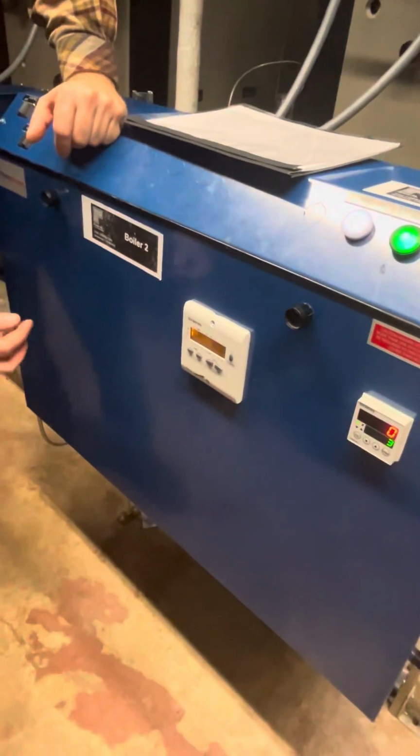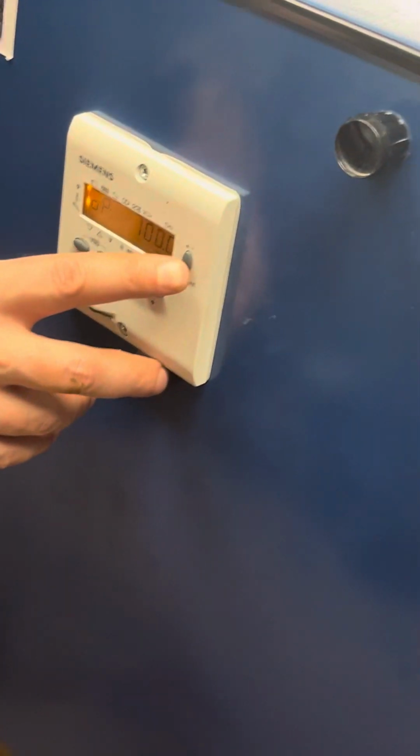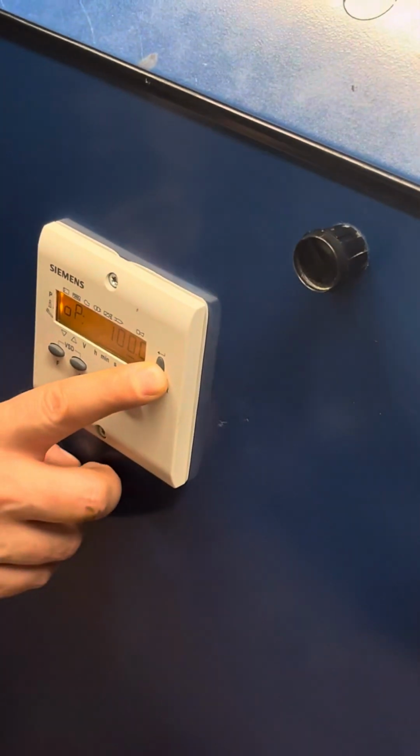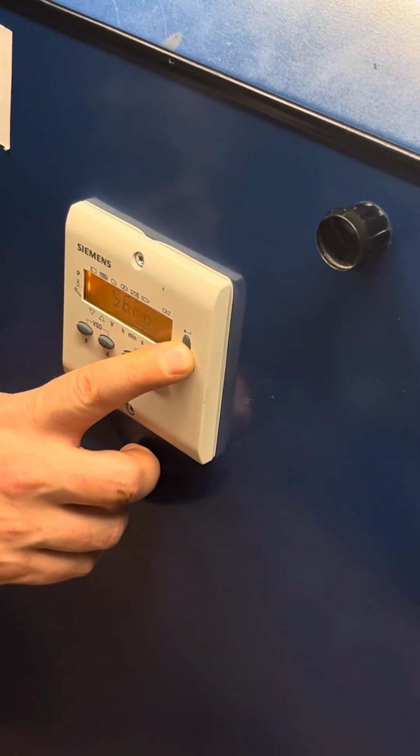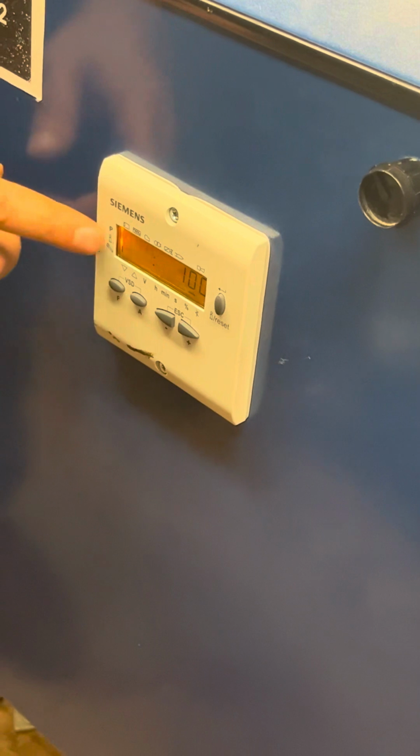You want to check your flame signal to see what the scanner is showing, similar to the fire eye. You hold down the reset button until you get to the service screen. The first thing that pops up while the burner is running is your flame signal. That's showing you 100% there.